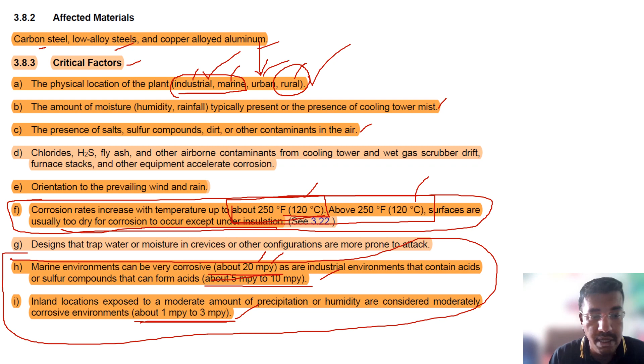Affected units of equipment: unpainted, uninsulated carbon steel and low alloy steel piping and equipment operating below 120 degrees centigrade where moisture can contact the surface are the most affected. If any piping surface is unpainted or uninsulated, it can come in direct contact with moisture and damage its surface. Uninsulated carbon and low alloy steel equipment with deteriorated paint or coatings. If any paint or coating is deteriorated, then it can happen. Equipment downwind of cooling towers and wet gas scrubbers. Equipment may be susceptible if cycled between ambient and higher or lower operating temperatures.